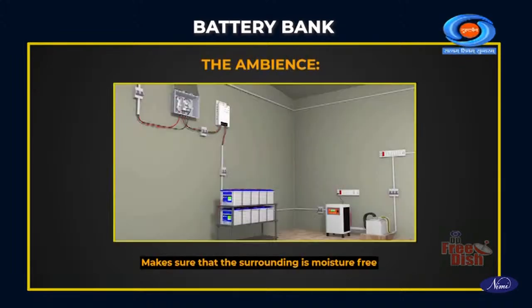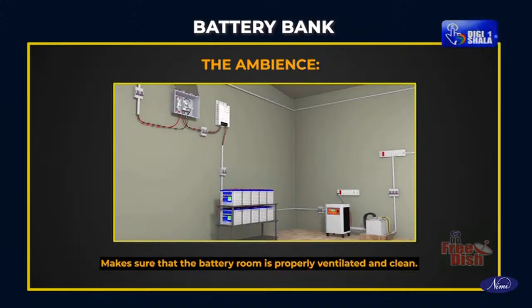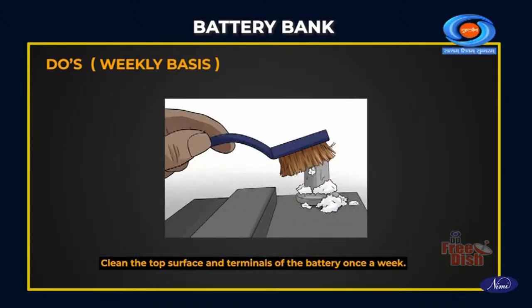Battery bank. The ambience. Make sure that the surrounding is moisture free. Make sure that the battery room is properly ventilated and clean. Do's. On a weekly basis, clean the top surface and terminals of the battery once a week.